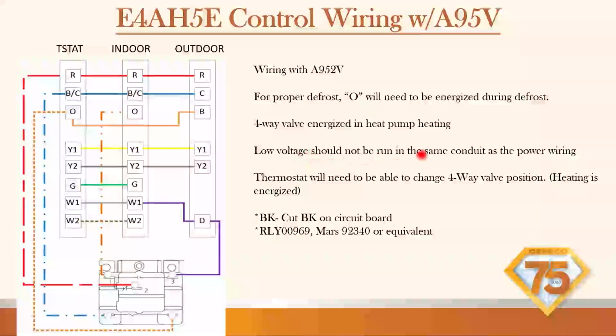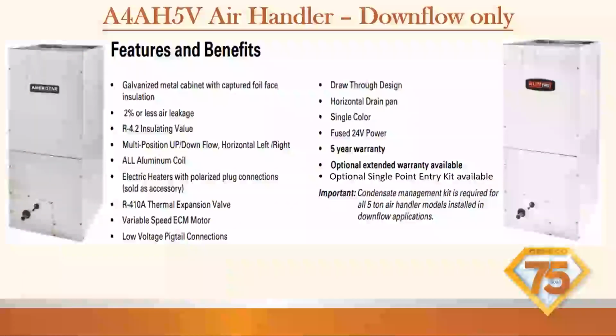Low voltage should not be running in the same conduit as the power wiring. Again, the thermostat will need to be able to change four-way valve position. Heating is energized. So we're going to have to tell the thermostat that we are energizing the reversing valve in heating. And this is that relay 00969. Nice picture of it. Hopefully that's pretty legible. You can always call in and we can send this to you too if you're missing paperwork. Here are our downflow only air handlers.